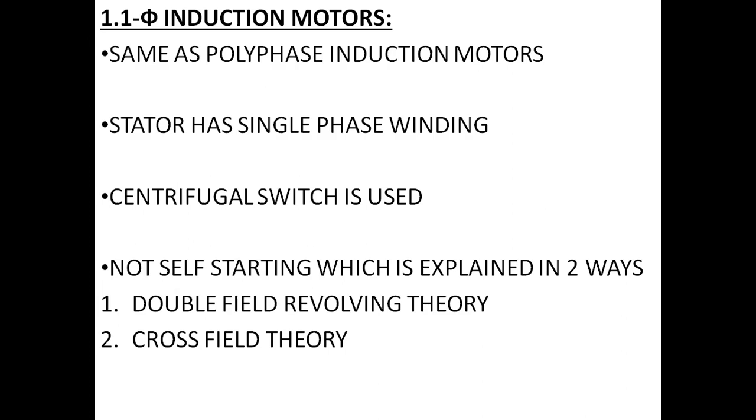Okay, so this switch is used to cut out the winding which is used for starting purposes. We are saying that the single phase induction motor is not self-starting, right? So to make it self-starting, we have to add another phase from outside, manually. This second phase is only used for starting purposes, so it should be cut out during the normal running of the machine.